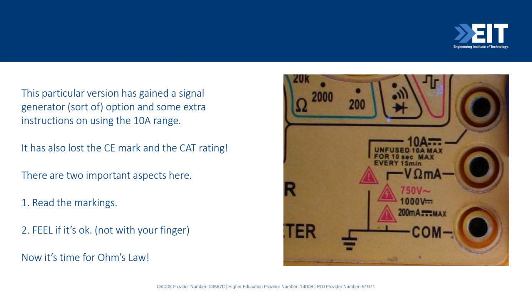So they're giving you a warning, even though they have no CE rating or CAT rating. They have the same voltage arrangements here. It's telling you what the maximum is. It's a warning sign. You see on this one, they left off the 500 volts. So somebody might think, well, hey, do I need to connect this common point to ground? It's amazing what small markings can lead people to think. You need to read markings on a meter, and you need to feel in your stomach, is this okay? You don't feel with your finger. You can find a lot of workshops where somebody will boast that they can measure 220 volts or 110 volts, depending on where you are in the world, with their finger by the amount of buzz they get. Not recommended. Okay, I promise you we're going to get some Ohm's law. Let's go have a look.